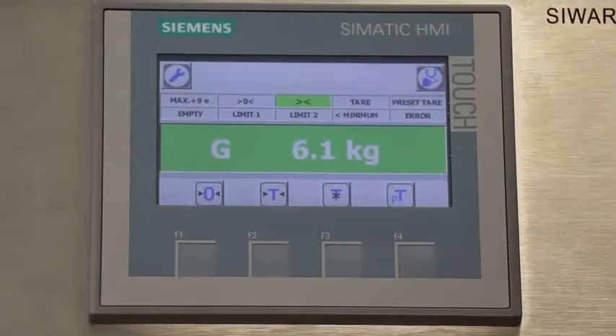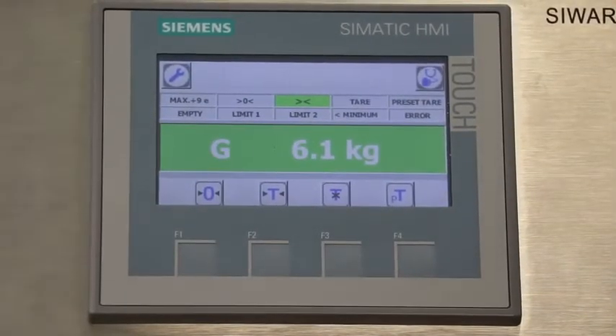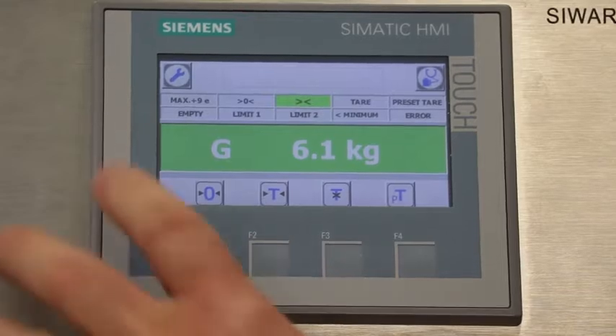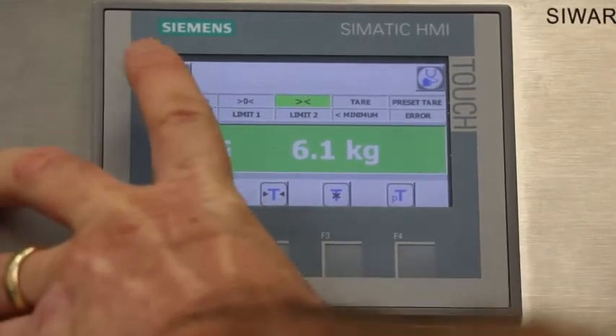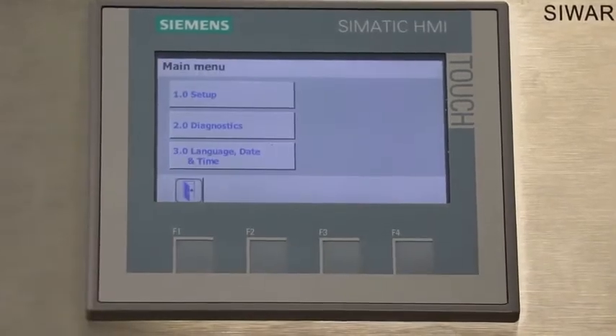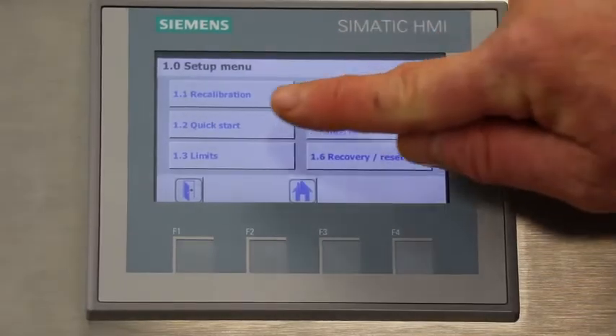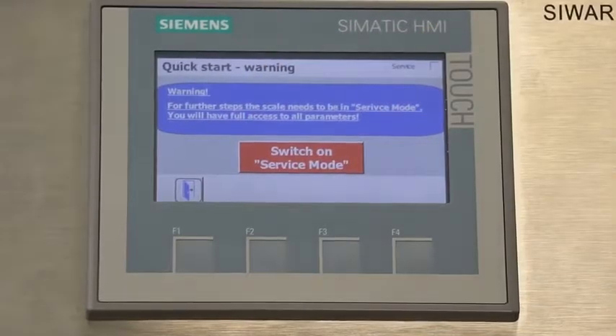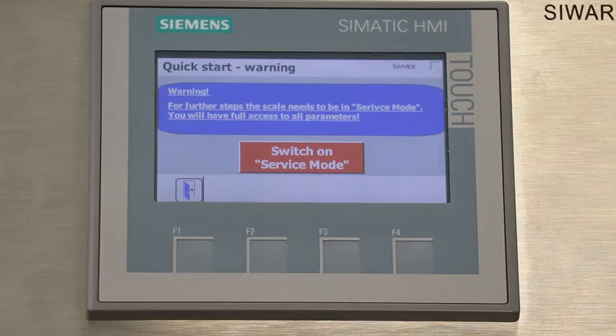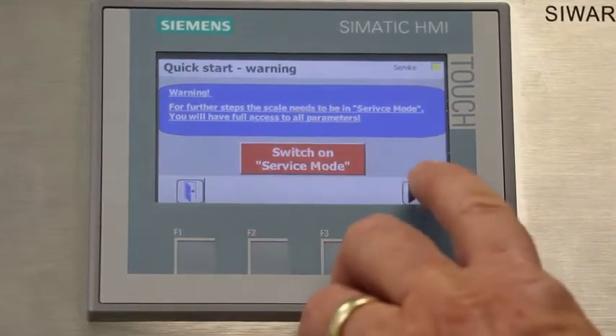You can see the SIWAREX WT231 has a graphic display for easy setup. To start the setup, we'll touch the wrench in the upper left corner. Next, we'll select Setup, and then Quick Start. To change any parameters in the WT231, you first have to enter the service mode. The service mode can be password protected to prevent accidentally changing a parameter that might affect the scale's accuracy. I've disabled the password feature in this unit, so we can go straight into the service mode.